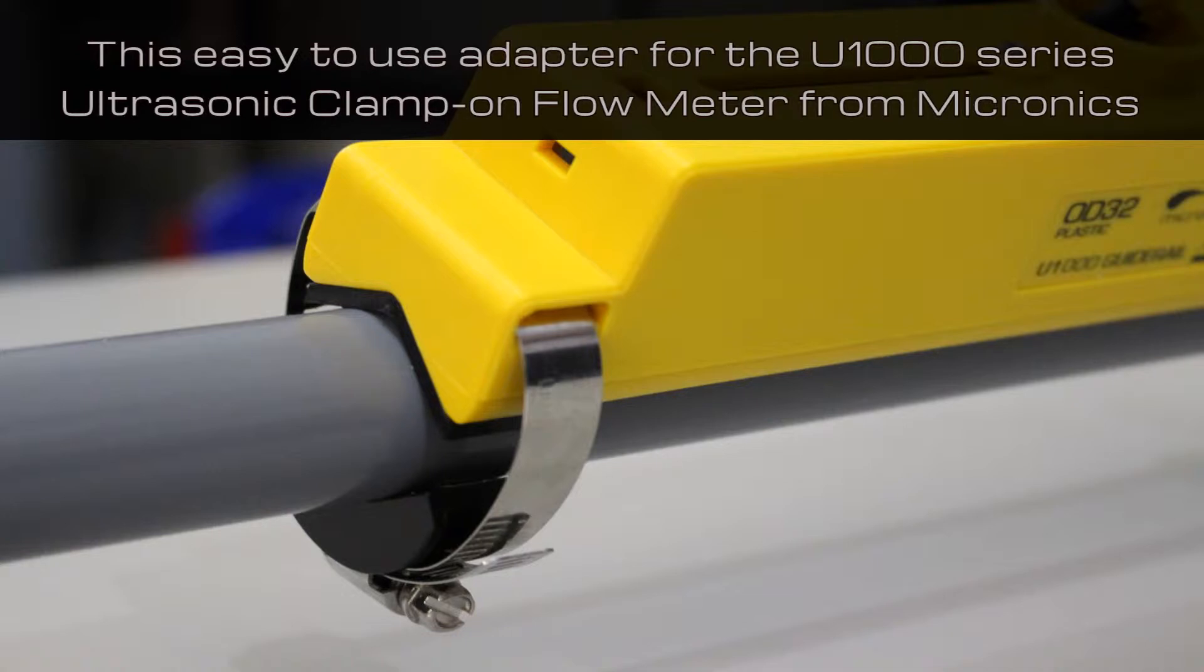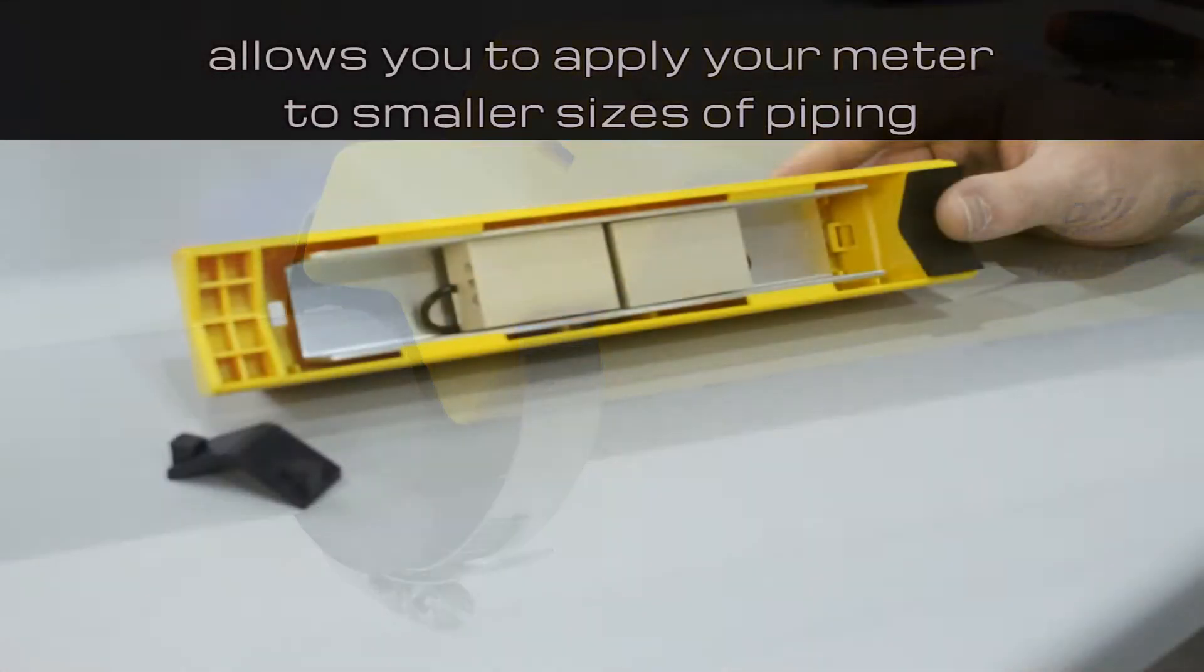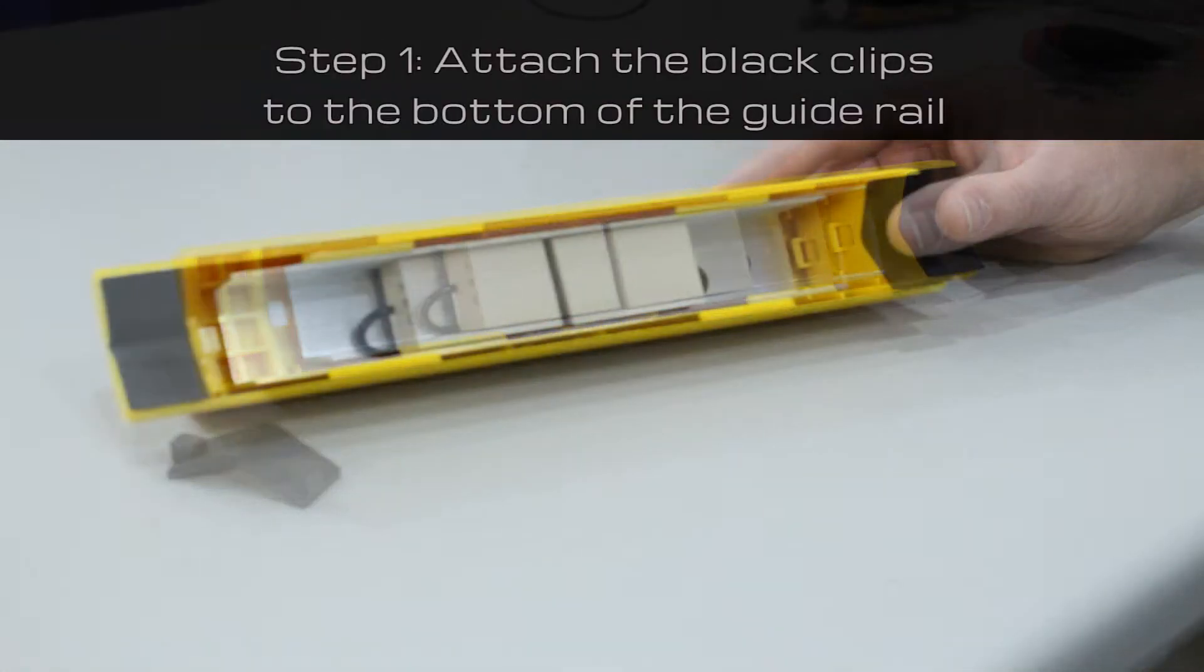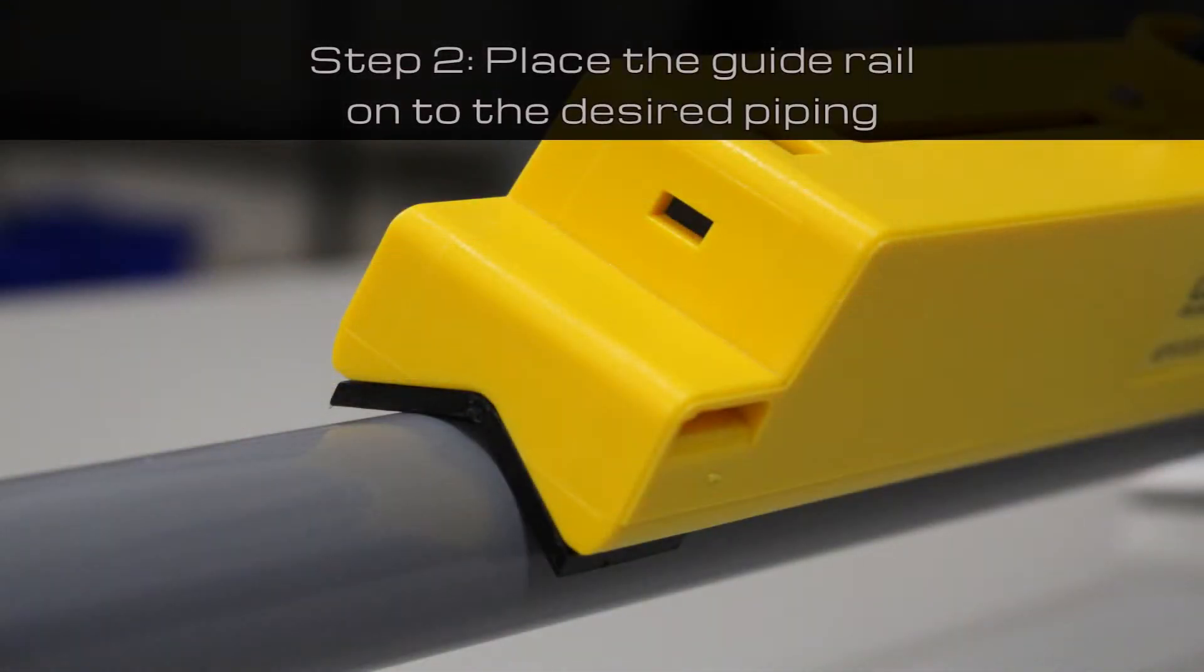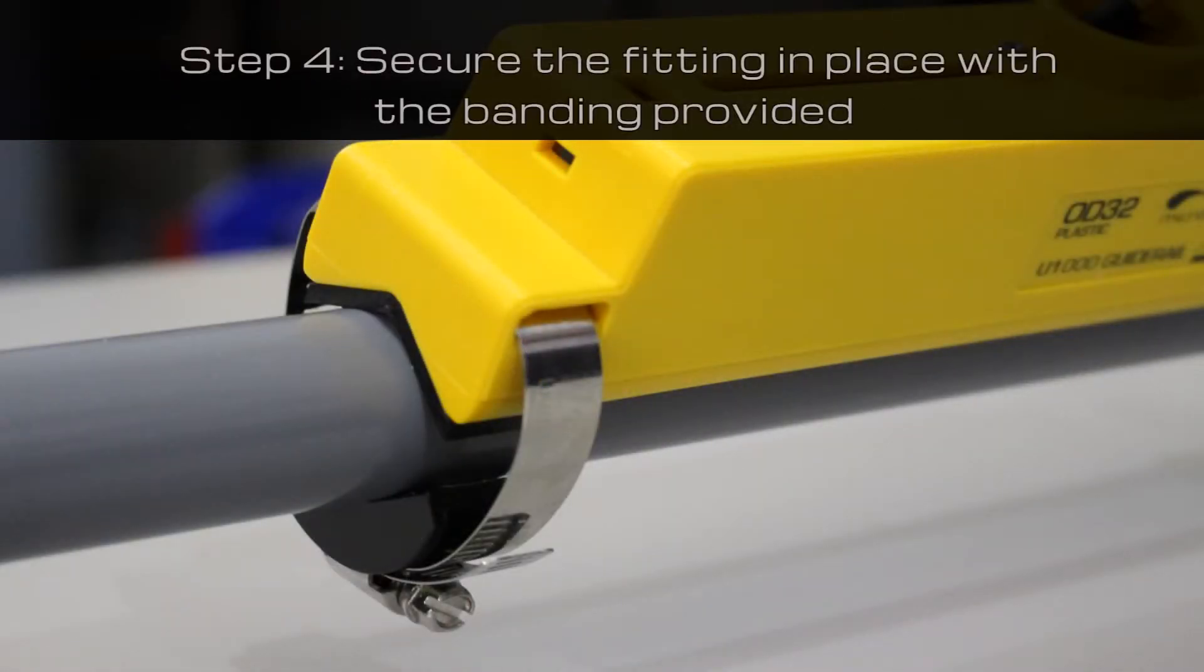This easy-to-use adapter for the U1000 series ultrasonic clamp-on flow meter from Micronics allows you to apply your meter to smaller sizes of piping. First, attach the black clips to the bottom of the guide rail, then place the guide rail on the desired piping. Attach the second black fitting to the bottom of your piping and secure the fitting in place with the banding provided.